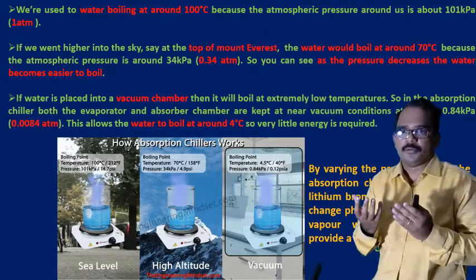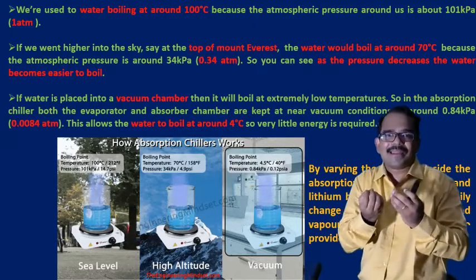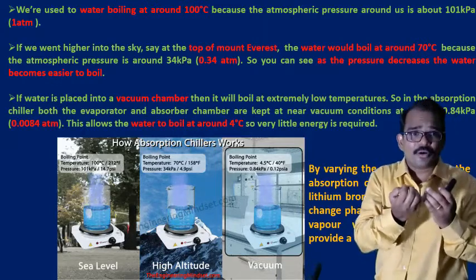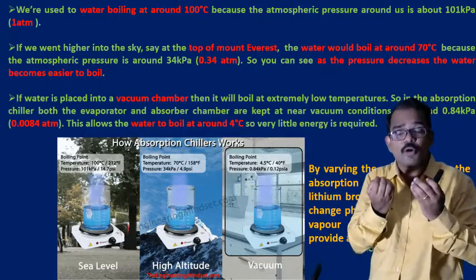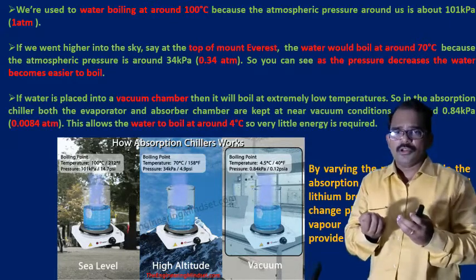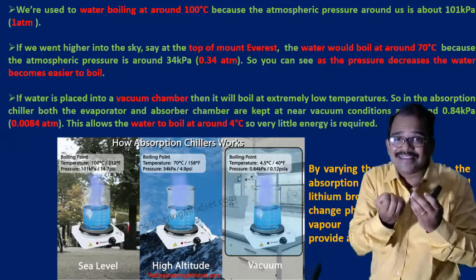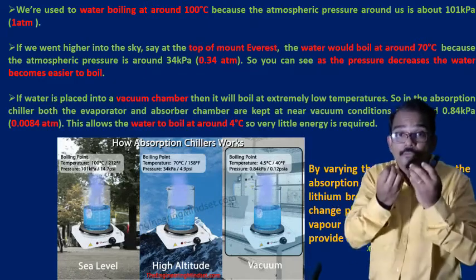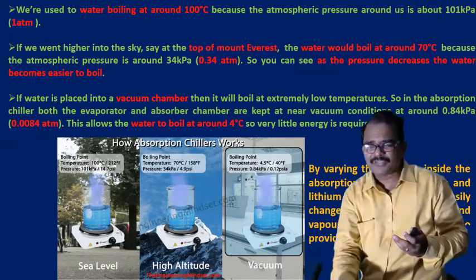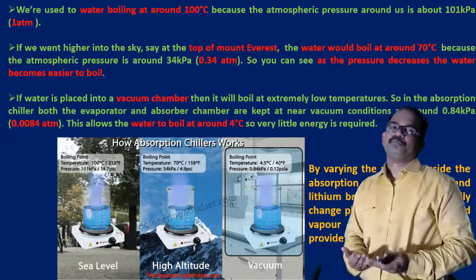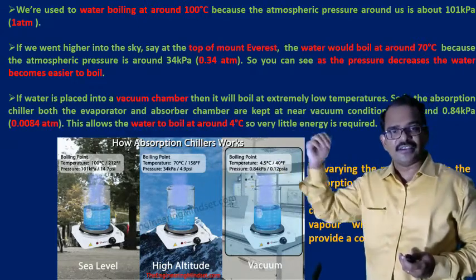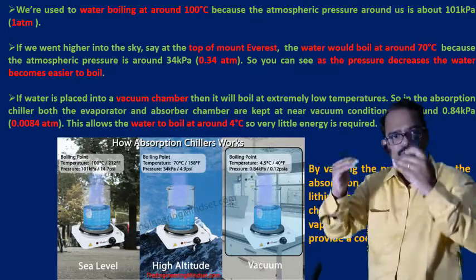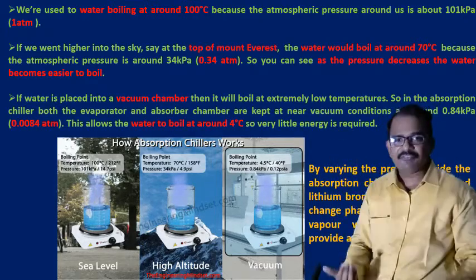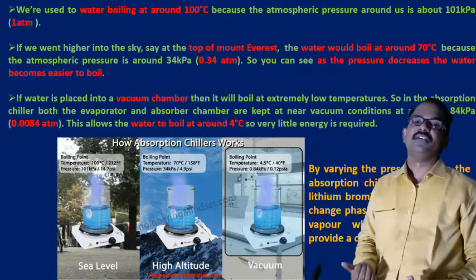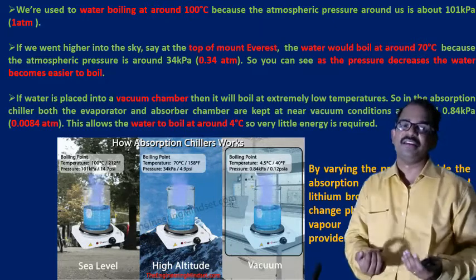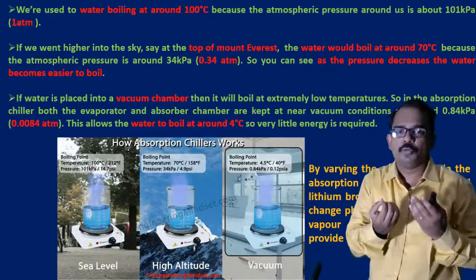In the absorption chiller, both the evaporator and absorber chambers are kept at near vacuum conditions. That is at around 0.84 kilopascals or 0.0084 atmospheres, which is negligible pressure. So the water boils at around 4 degrees centigrade. The water boils at around how many degrees centigrade? 4 degrees centigrade. You can see as the pressure becomes negligible, the boiling point also becomes negligible. So when the pressure is 1 atmosphere, the boiling point is 100 degrees centigrade. When the pressure is 0.34 atmospheres, the boiling point reduces to 70 degrees centigrade. And when the pressure is reduced even below 0.0084 atmospheres, the boiling point of the water reaches 4 degrees centigrade. So very little energy is required now to boil off the water.